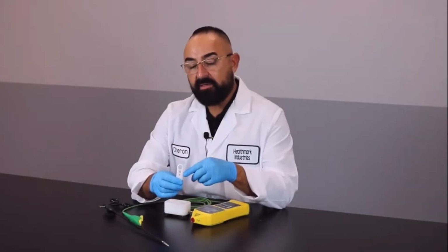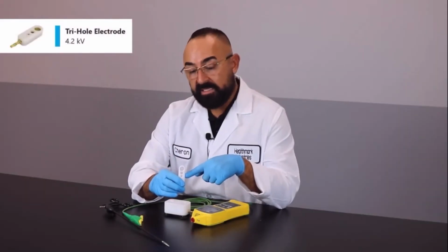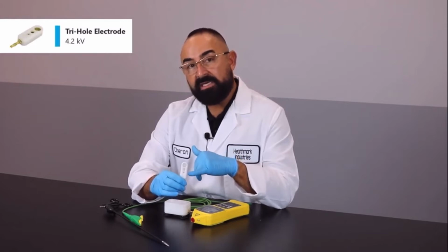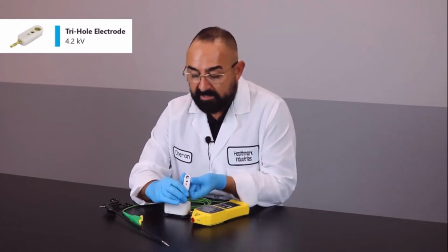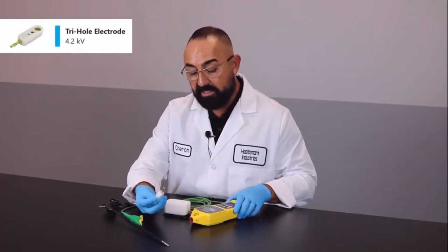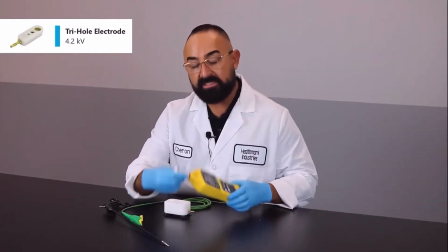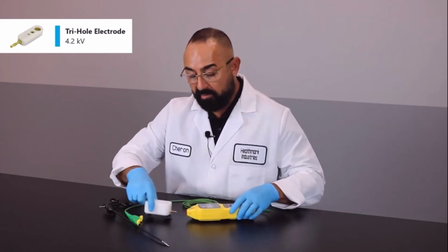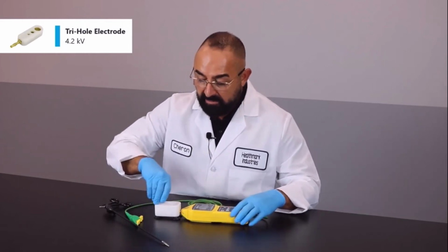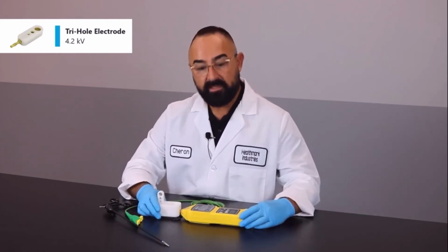This one is called the tri-hole accessory. You're going to notice that there's 3 different holes in this accessory. The first one is a 10 millimeter diameter for laparoscopic. The second one in the middle is for 5 millimeter laparoscopic. And the third one is for 3 millimeter laparoscopic. There is two different ways that this can be used. This can go directly into the unit itself, like so, or ideally into the saddle block, like this.